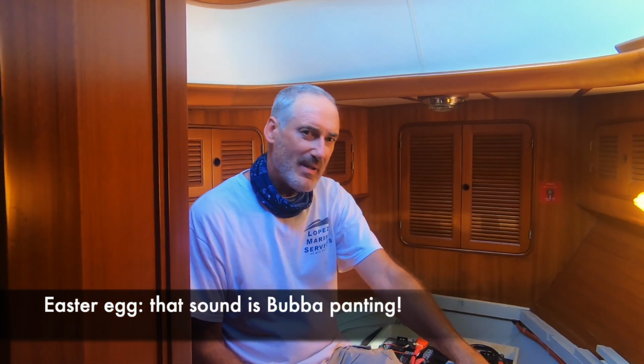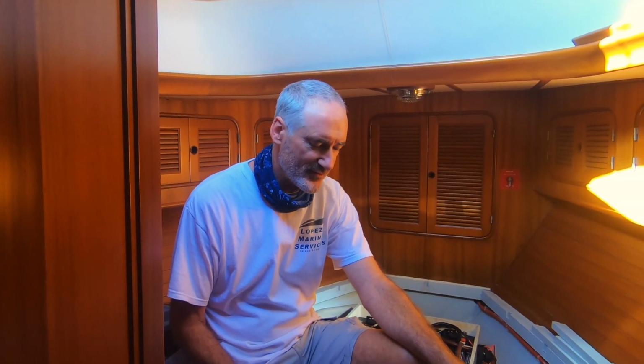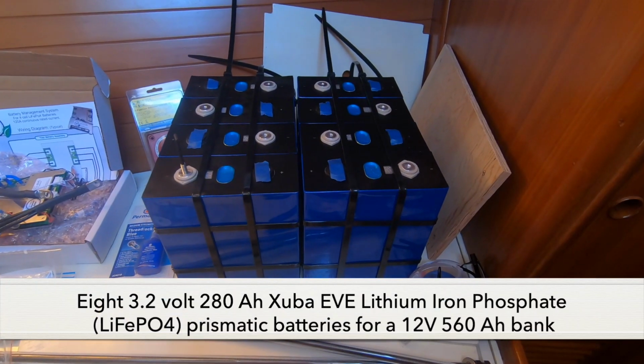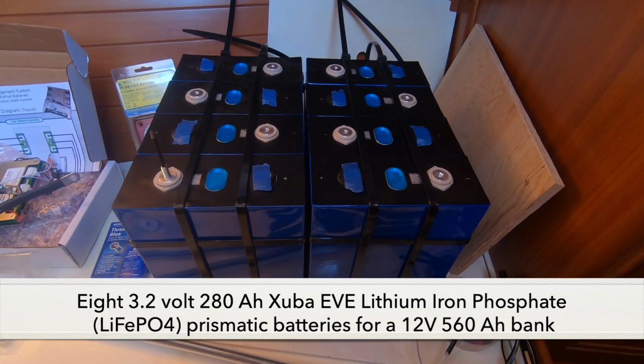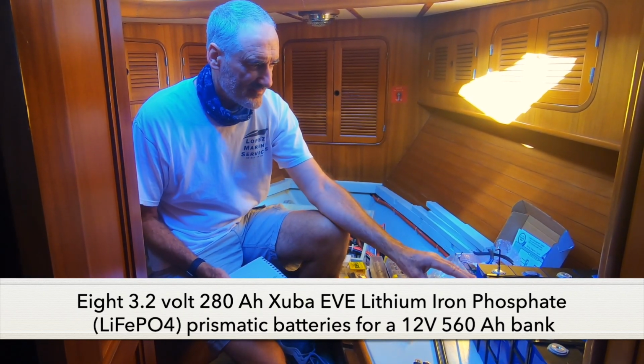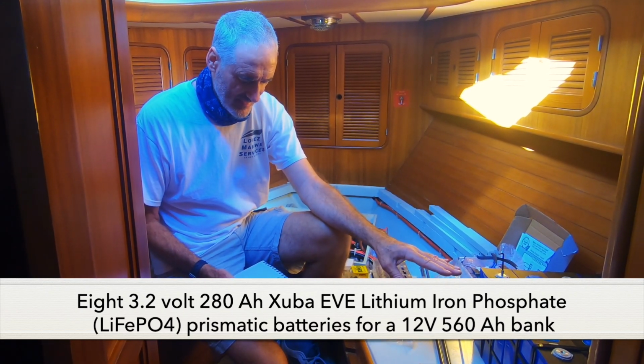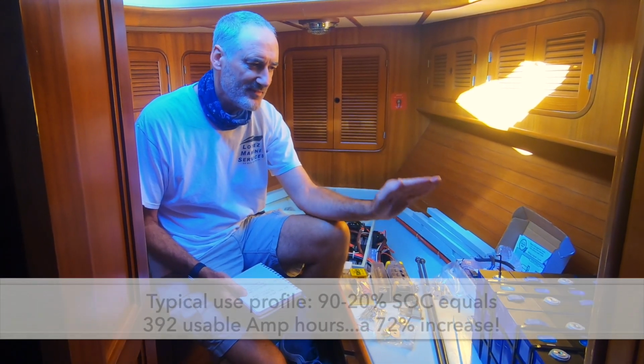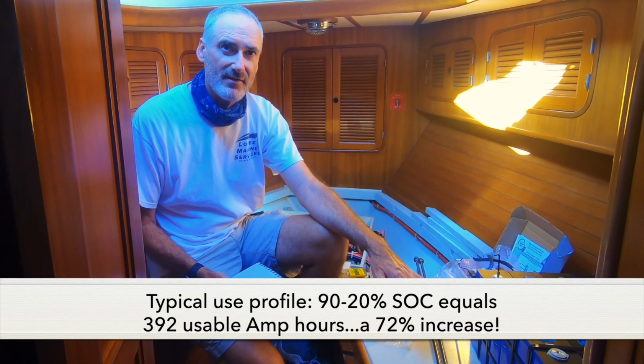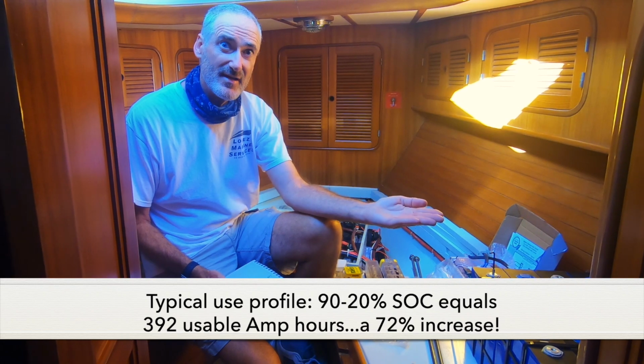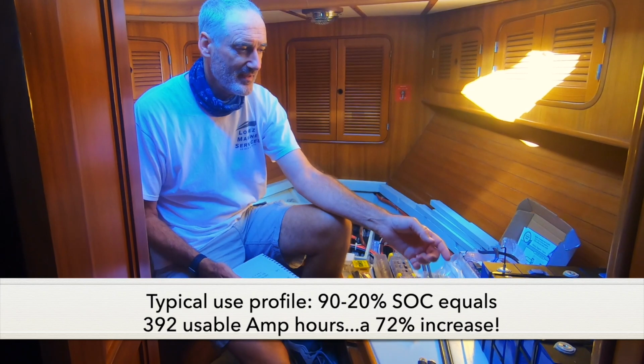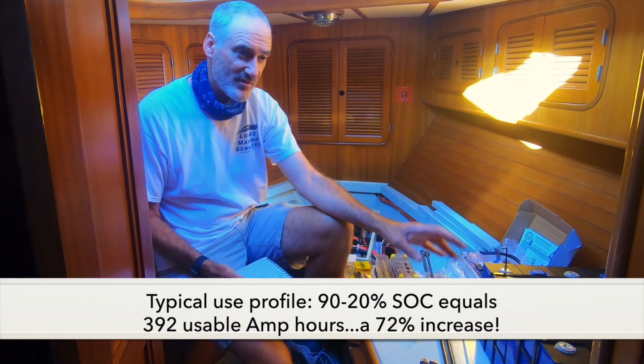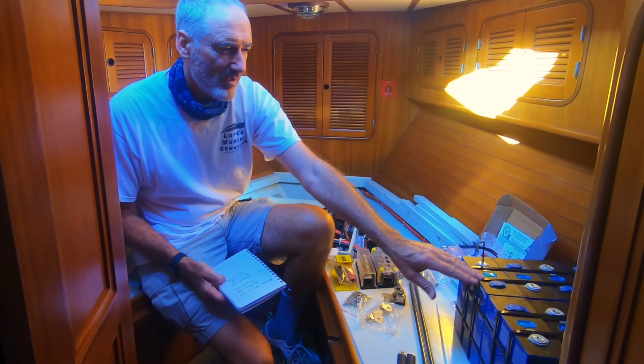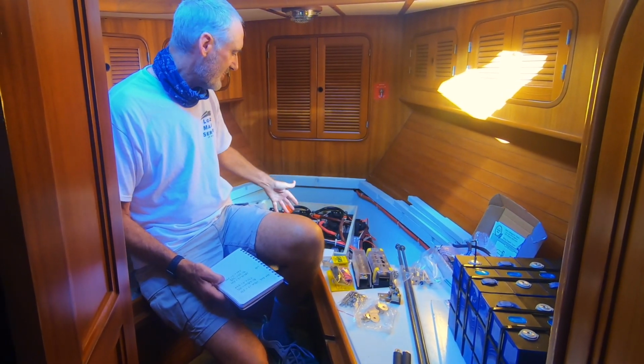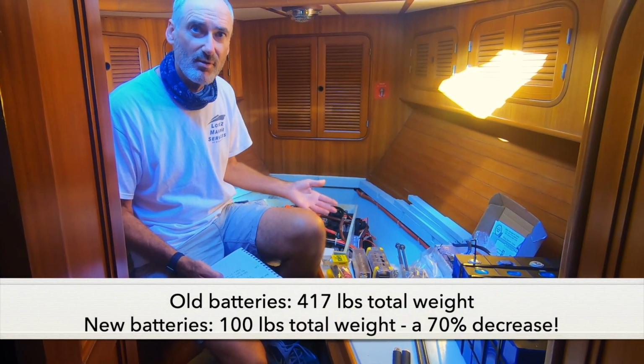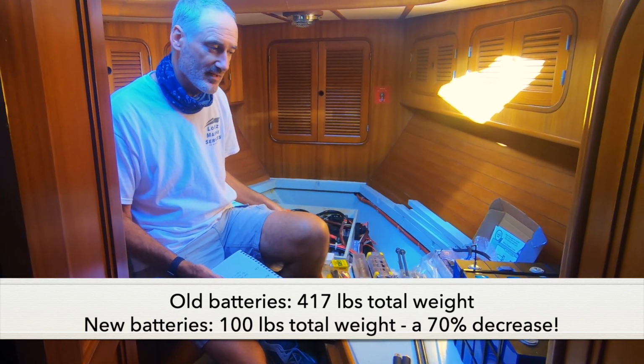This new bank here is the new lithium iron phosphate chemistry, small packs of 280 amp hours at 3.2 volts. You add 4 together and you get a 12-volt battery, and I've got 2 of these, giving a total of 560 amp hours. With lithium iron phosphate you can use these down to 20% state of charge and still have plenty of life left. Since they'll probably get charged up to about 90%, going from 90 to 20 is a 70% difference. Multiply 560 amp hours by 70% and that gives you 392 amp hours usable. So this small combination of batteries takes up a third of the space and a fraction of the weight, but will give us almost double the usable capacity compared to the original house battery bank.